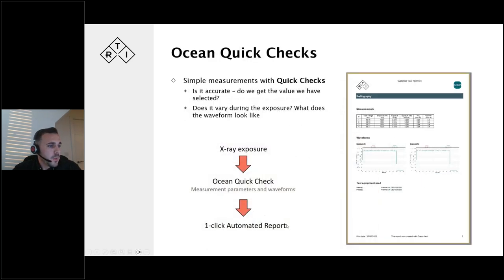So what I just demonstrated is simple measurements with quick checks. You may walk up to the X-ray system and just want to check: is it accurate? Do we get the values we selected? Is the dose and the KV what I expect it to be? And is it varying during the exposure? What does the waveform look like?